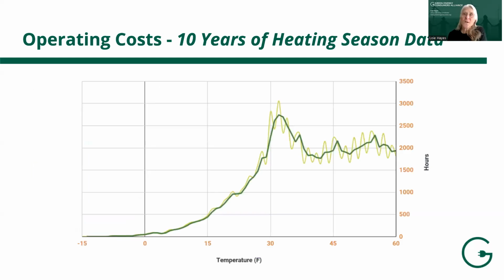Now let's look at the operating costs of a heat pump. There are several factors, and I first want to orient you to the weather, which is one of 3 factors. There's weather, there's efficiency, and there's the fuel cost. Those are the 3 things that we'll look at. So first, looking at weather. This is 10 years of heating season data from New England. This is the temperature, and this is the hours of the heating season that you are at that temperature. So we have roughly 2,000 hours at 60. We have roughly 2,500 at 32. So you see the majority of the winter, you're in that 30 to 60 degree range. And then say, 20 to 30% of the winter, you're in colder temperatures.